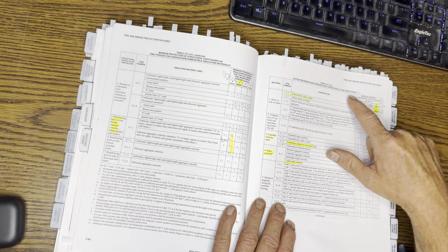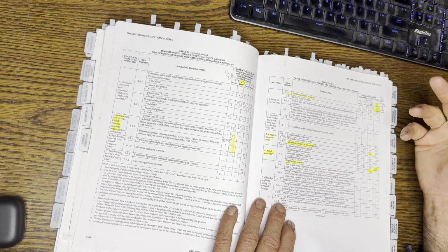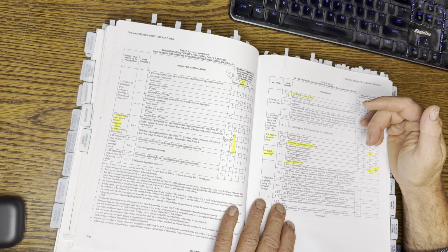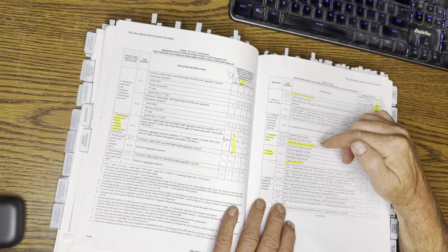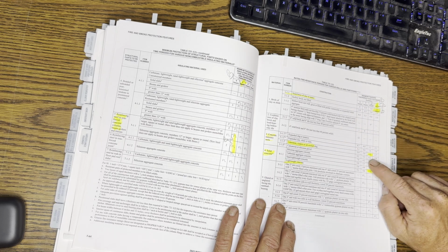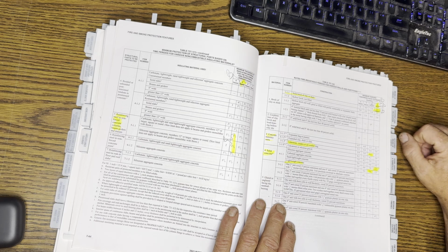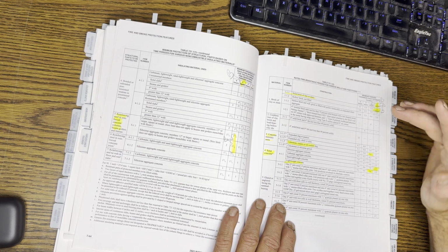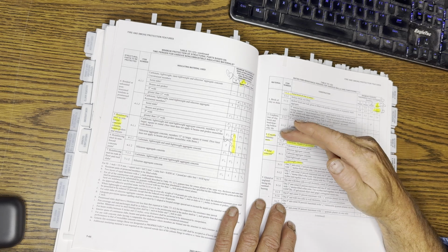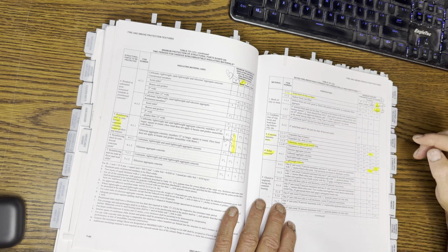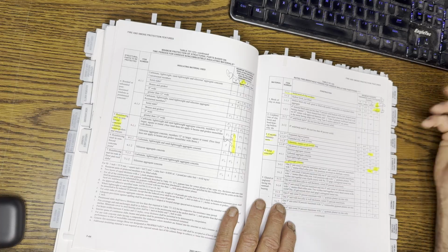So let's say you have a question. You have concrete masonry units, CMUs. They're made out of limestone cinders, air-cooled slag, and so on. They're 2 hours. How thick does it have to be? 4 inches. There it is. That's how you'd solve it. Or the question would say, you have a wall made out of concrete masonry units, limestone cinders. They're 4 inches thick. What's the rating? And the number is 2 hours. That's how you'd look that up.